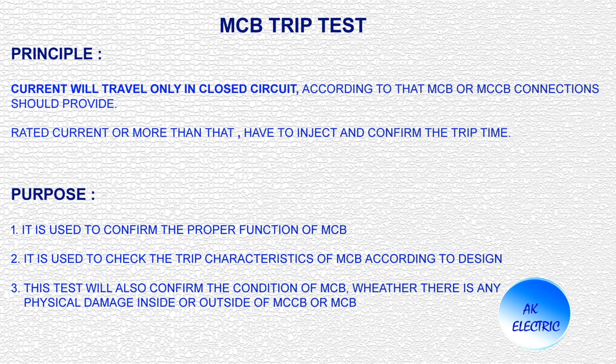First let's see the principle of this test. Current will travel only in a closed circuit; according to that, MCB or MCCB connections should be provided. Then rated current or more than that is injected to confirm the trip time.